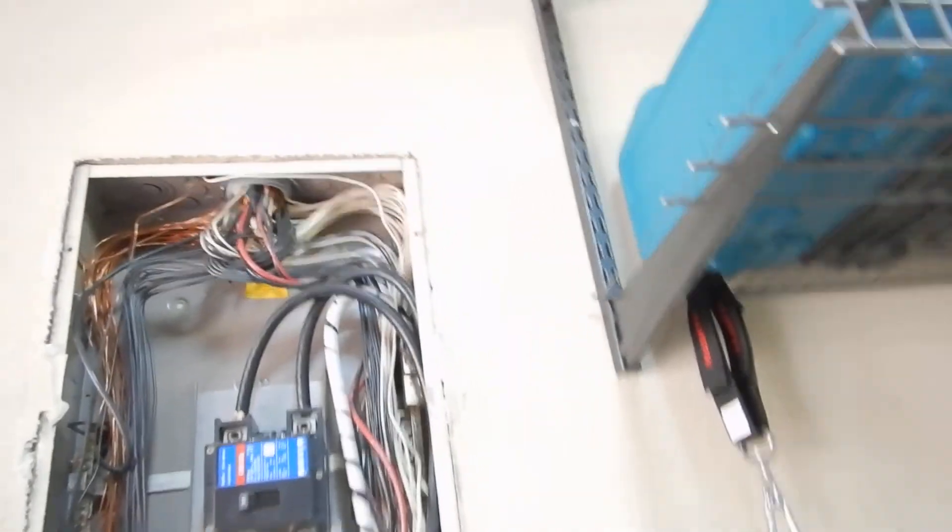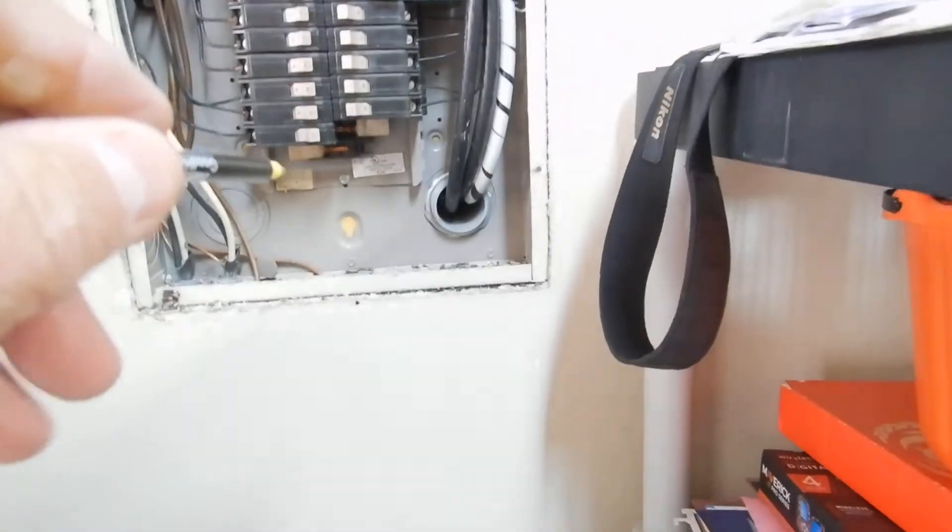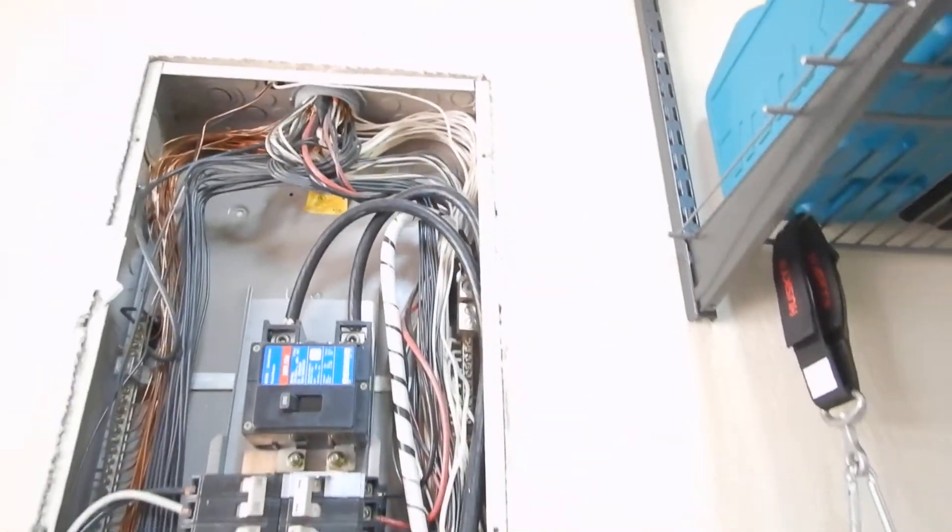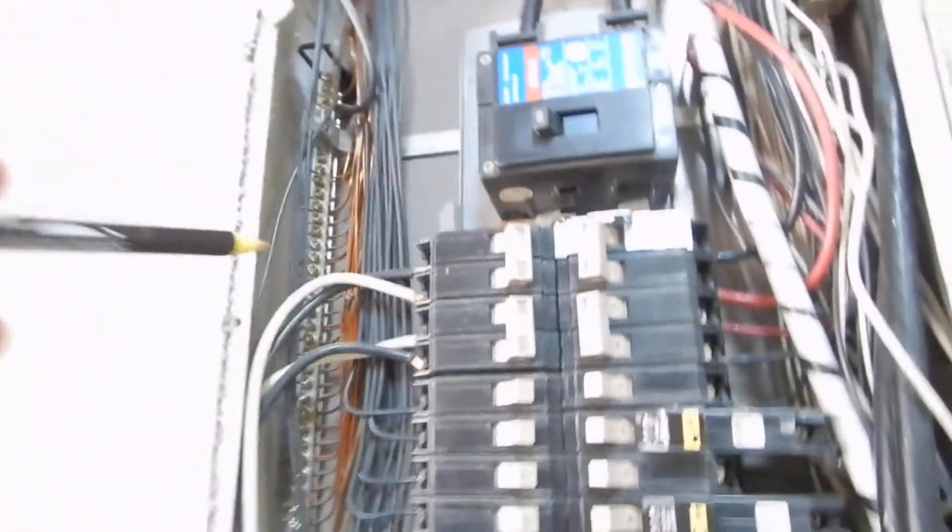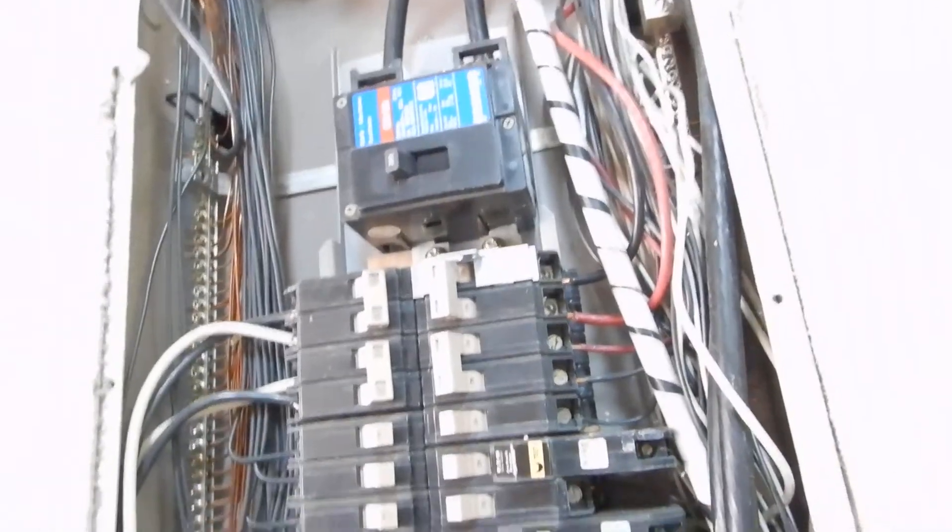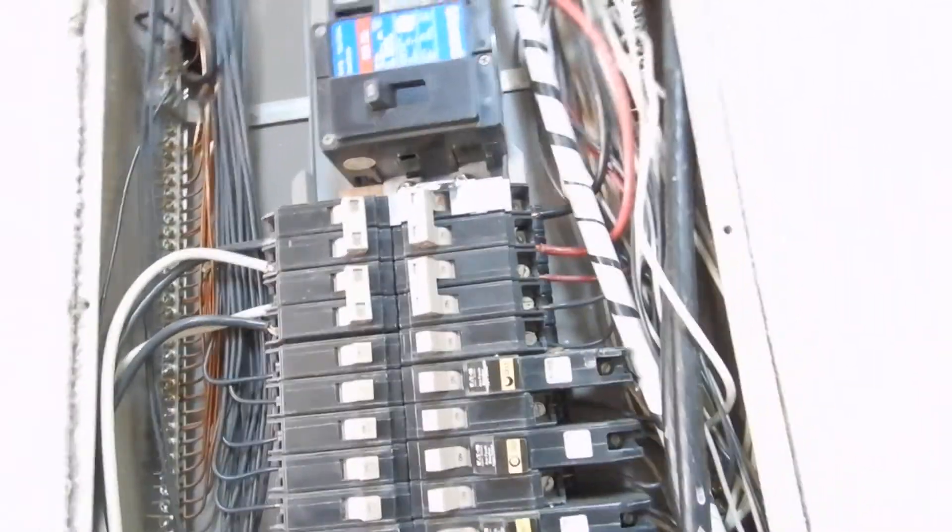So anyway, so what did we learn? We learned that our bonding location is not labeled. We learned that our cabinet was screwed into place. We learned that we've got bundling and our cables are touching the cabinet covers. We learned that we've got some white hots that aren't wrapped in black tape. And that's about it.